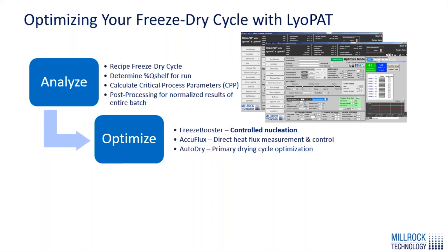We can then look to optimizing the run using the various optimization features: FreezeBooster for controlled nucleation, AccuFlux for direct heat flux measurement and control post-nucleation, and AutoDry for primary drying cycle optimization. Two out of three of these features are built around optimizing the freezing side of the recipe — only AutoDry works in primary drying. The foundation of an optimized protocol occurs in the freezing phase, when you're developing the frozen crystal structure that determines many critical quality attributes of your final dried cake.